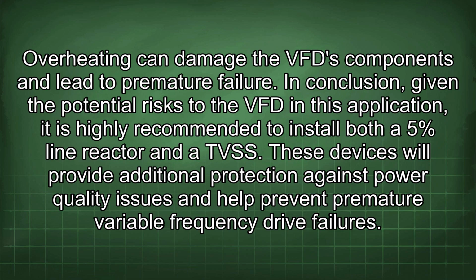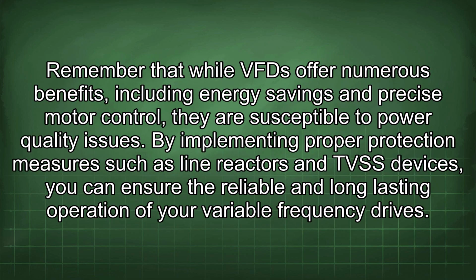In conclusion, given the potential risks to the VFD in this application, it is highly recommended to install both a 5% line reactor and a TVSS. These devices will provide additional protection against power quality issues and help prevent premature variable frequency drive failures. Remember that while VFD offer numerous benefits, including energy savings and precise motor control, they are susceptible to power quality issues. By implementing proper protection measures such as line reactors and TVSS devices, you can ensure the reliable and long-lasting operation of your variable frequency drives.